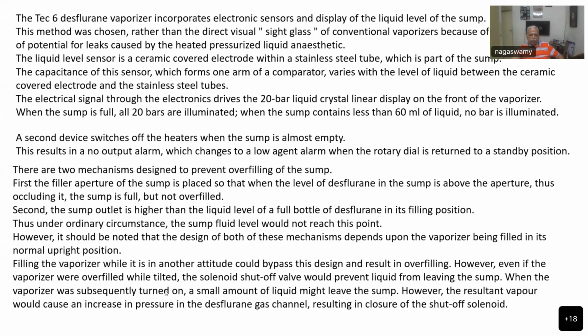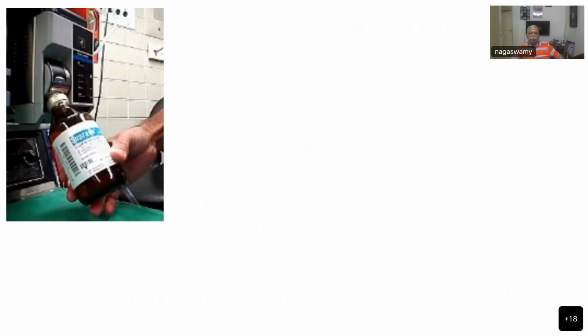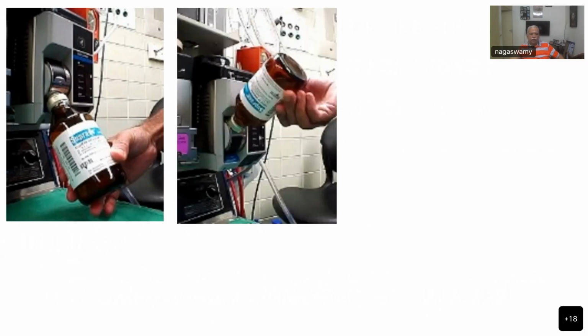However, even if the vaporizer were overfilled when tilted, the solenoid shutoff valve would prevent liquid from leaving the sump. When the vaporizer was subsequently turned on, a small amount of liquid may leave the sump. However, the resulting vapor would cause an increased pressure in the desflurane gas channel, again resulting in closure of the shutoff solenoid valve. So from all this description, we can understand that the shutoff solenoid valve, which is very close to the outlet of the sump, plays a very major role in preventing excess desflurane being delivered. So this is how the filling happens, and you can see why it cannot be overfilled.